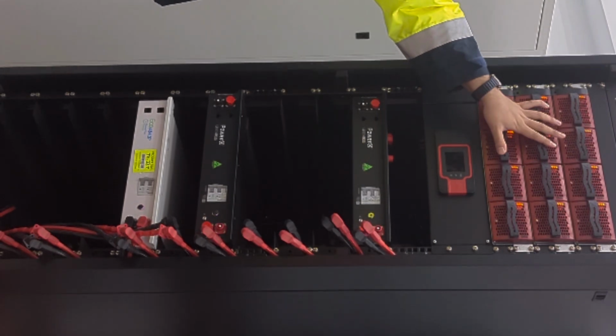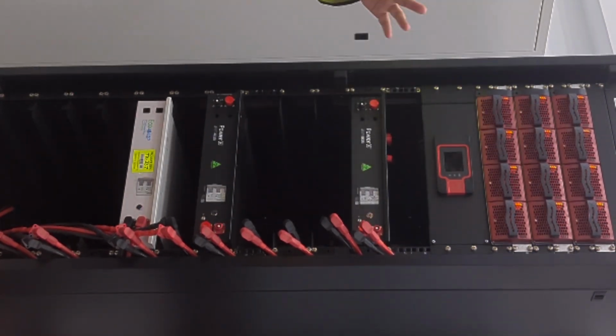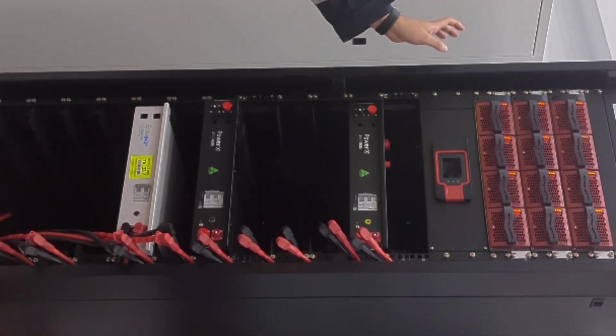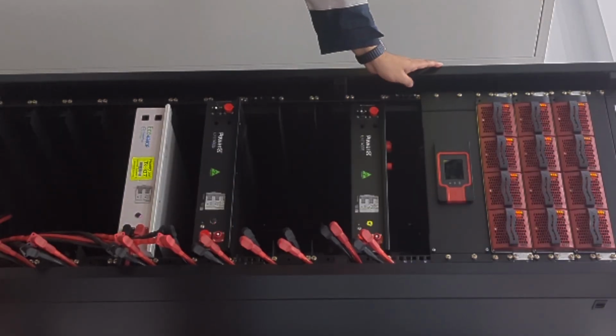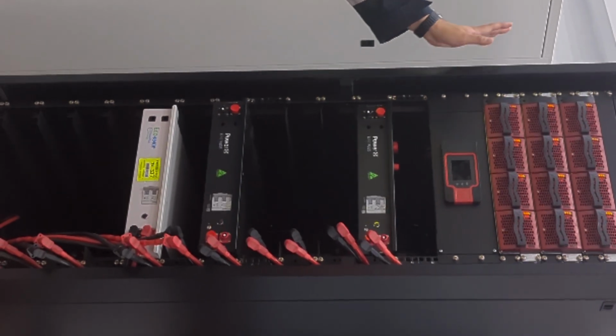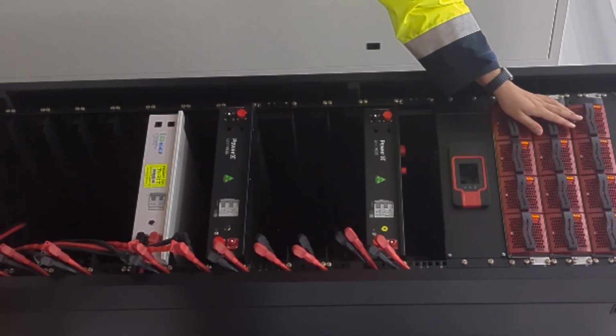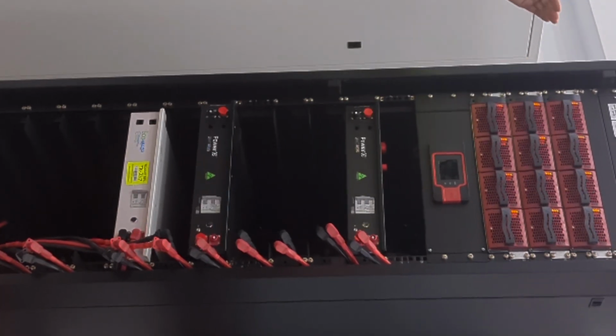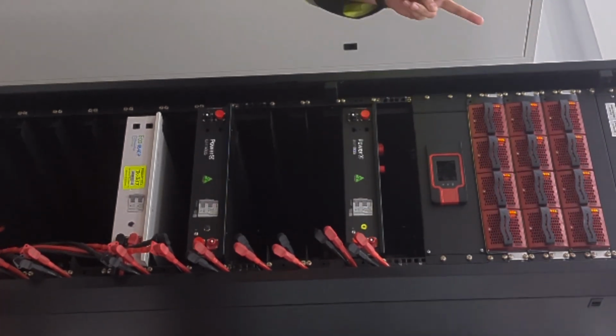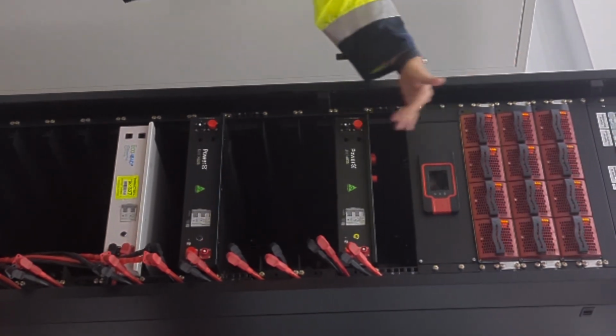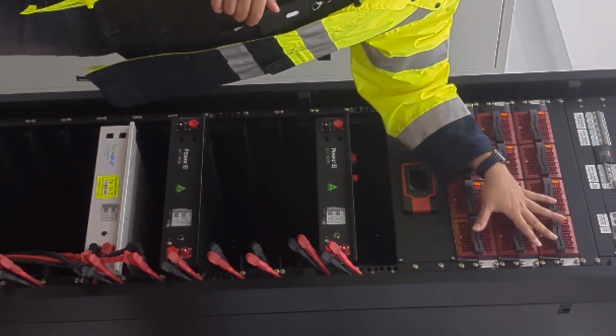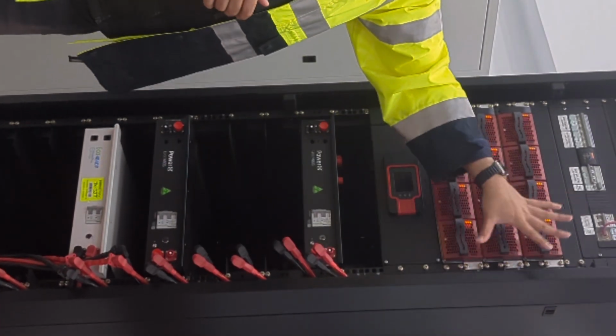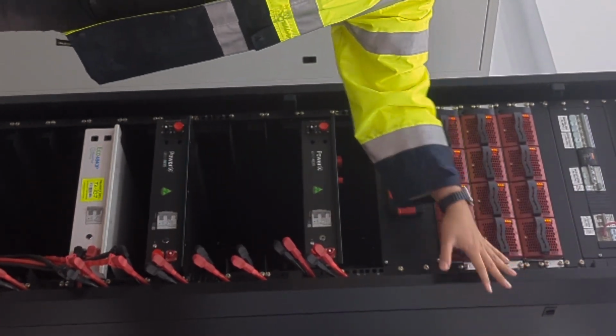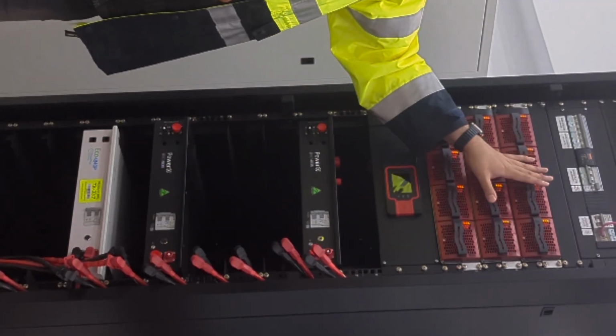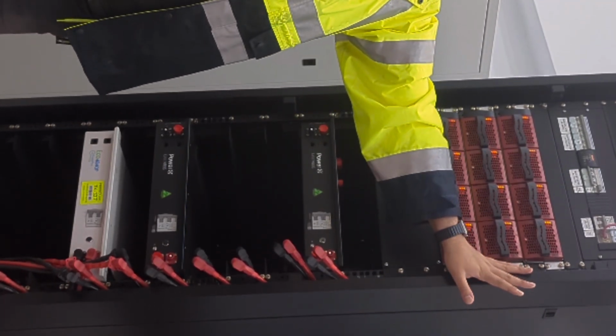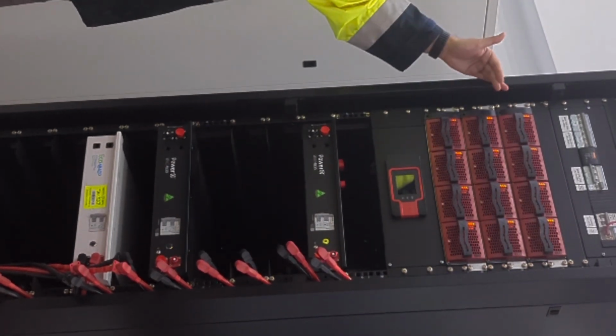can't replicate this function. So this function of a pure UPS is, I think what Shane was referring to before, is how you sidestep grid connection requirements. Imagine if this was a single phase spur line in the middle of the country. You can bring your single phase into it on what we call our rectifier side, charge the batteries, and still have a 3-phase microgrid on the other side. You could have 3-phase inverters sitting on the microgrid side controlled by the controller. You can have 3-phase loads on the microgrid side, but you've still got a single phase grid connection.